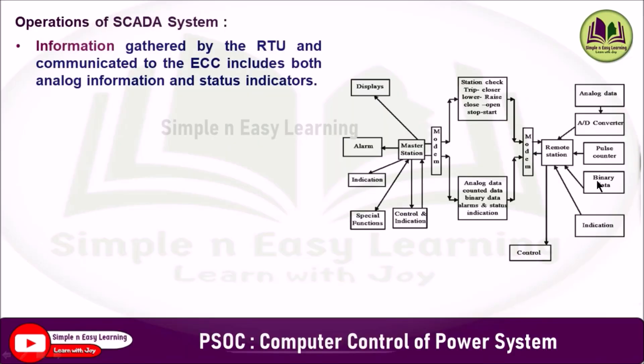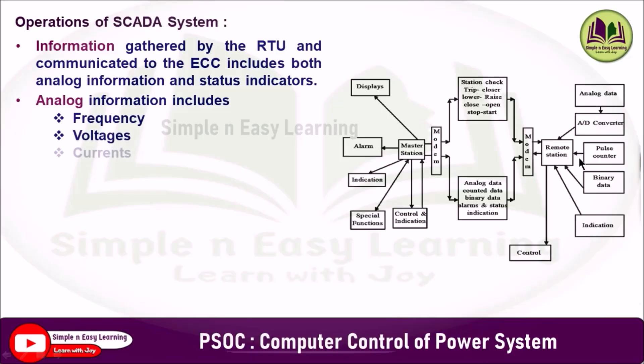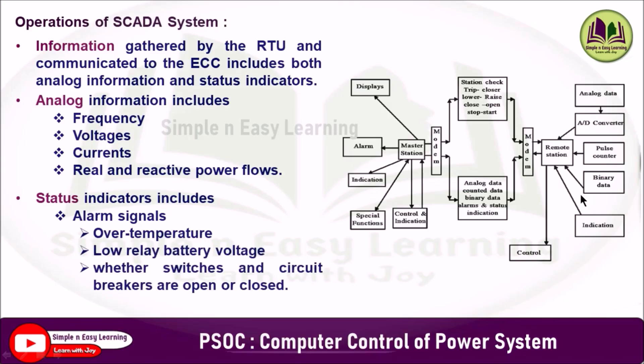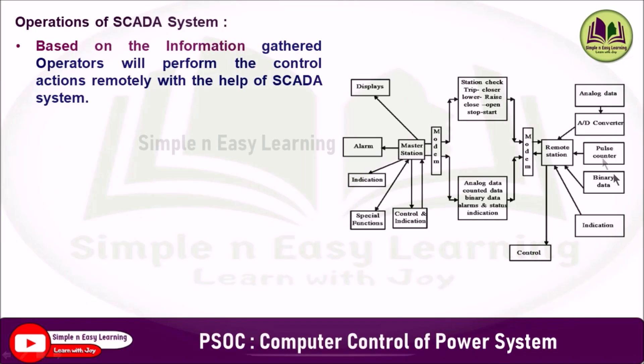Information gathered by the RTU and communicated to the ECC includes both analog information and status indicators. Analog information includes frequency, voltages, currents, and real and reactive power flow. Status indicators include alarm signals such as over-temperature, low relay battery voltage, and whether switches and circuit breakers are open or closed. Based on the information gathered, operators perform control actions remotely with the help of the SCADA system.